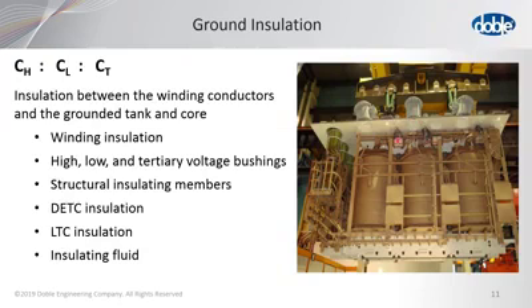Each one of these will be energized and tested to ground during the high voltage test usually. That's where the DETC is usually located, in the high voltage winding. Now the load tap changer is shown here, and these of course are energized when the low voltage winding is energized, and they will be stressed during that time.